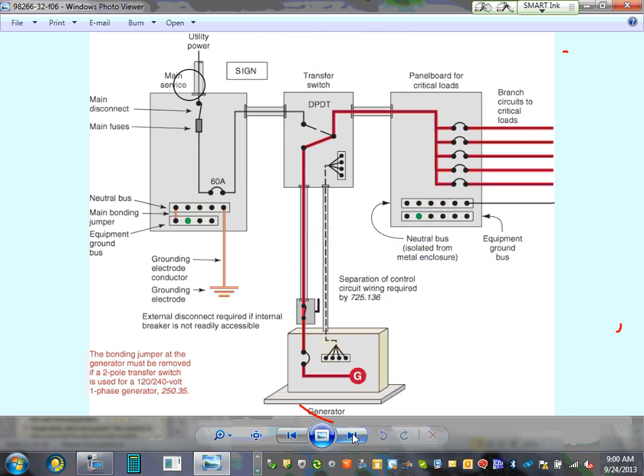Now, when you lose power, here's what happens. Very simple. Can you guys see how this flipped? Look at this. It flipped down to the generator. Two things happen when you lose power. The sensors here are sensing the power. When they sense that the power is lost, they send the signal directly to the generator. Say, Mr. Generator, fire. Start.